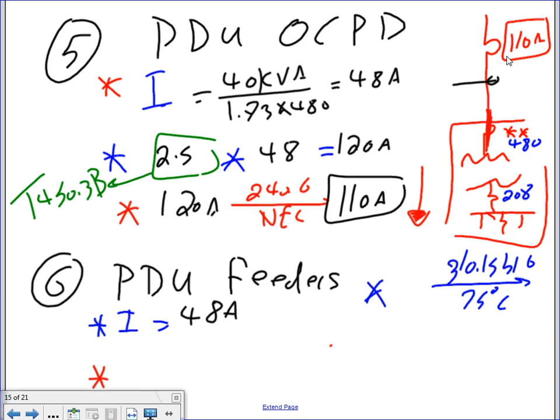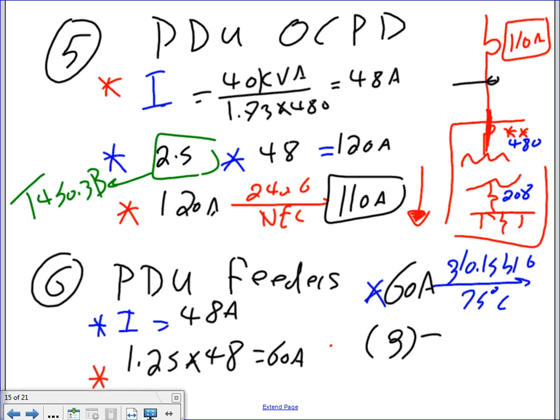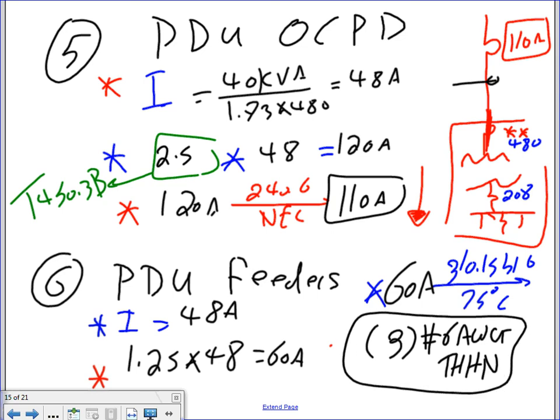So then you're going to have 1.25 times 48. What do I have? 60 amps, right? And then I'm going to take my 60 amps here, and from my 60 amps I'm going to go to table 310.15(B)(16), and that will give me 3 conductors, number 6 AWG THHN. The same as for the UPS, right? The feeder that feeds the UPS is the same as the feeder that's coming out of the UPS, in this case.